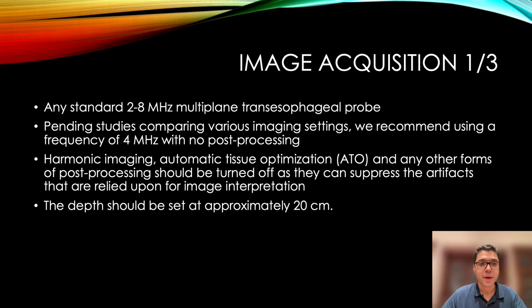Any standard 2 to 8 MHz multi-plane transesophageal probe can be used to perform transesophageal lung ultrasound. Pending studies comparing various imaging settings, we recommend using a frequency of 4 MHz with no post-processing. Harmonic imaging, automatic tissue optimization, and any other forms of post-processing should ideally be turned off, as they can suppress the artifacts that are relied upon for image interpretation. The depth of the field should be set at approximately 20 cm.